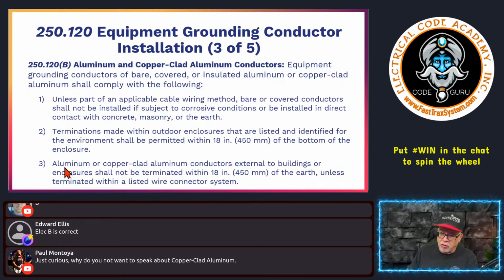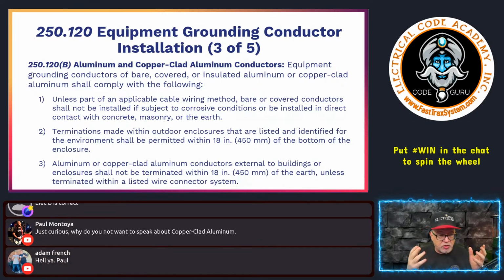All right, so the next, third one says aluminum or that other conductor external to buildings or enclosures shall not be terminated within 18 inches of the earth unless terminated within a listed wire connector system. That is a system that is designed for termination in the location where this termination is taking place. So it may be encapsulated, it may be sealed. So that would be a specific application.